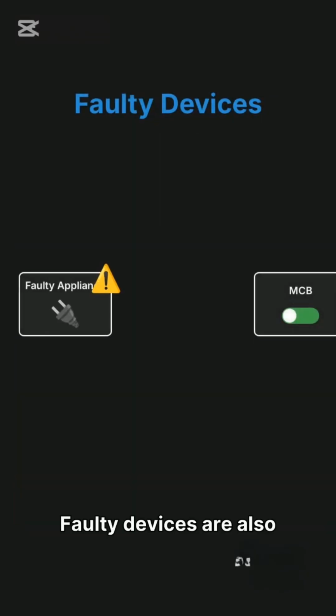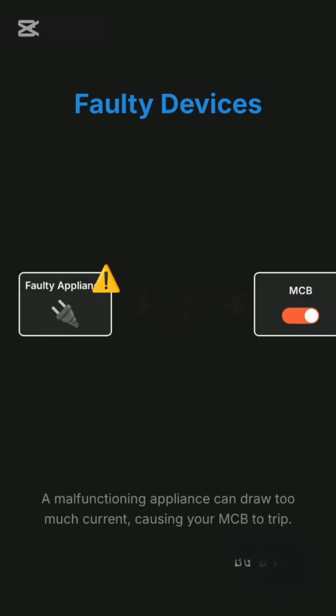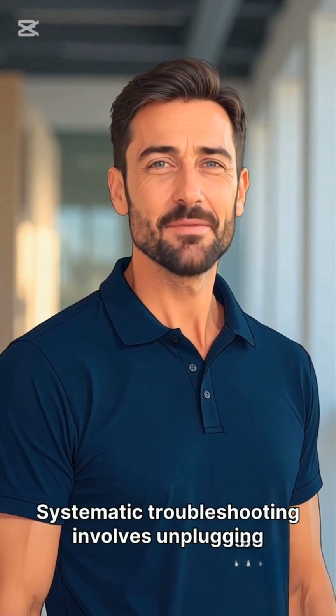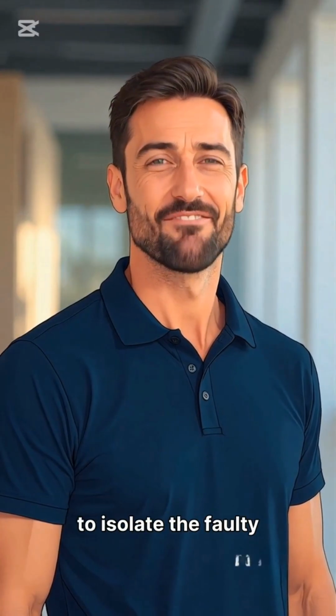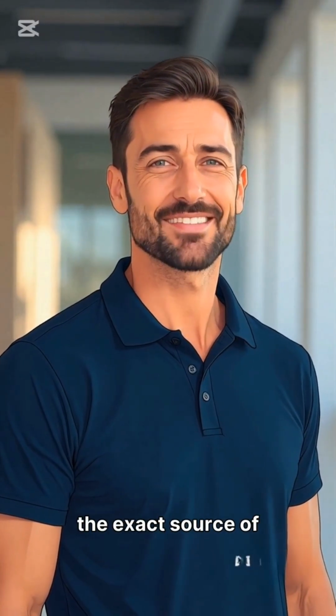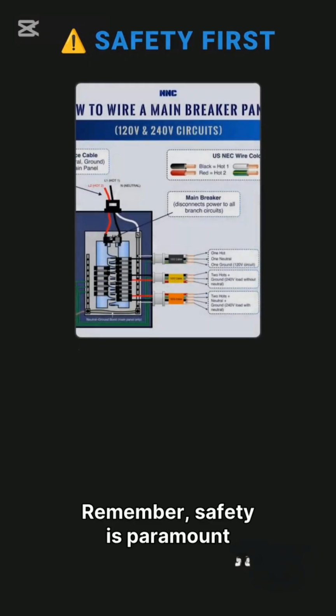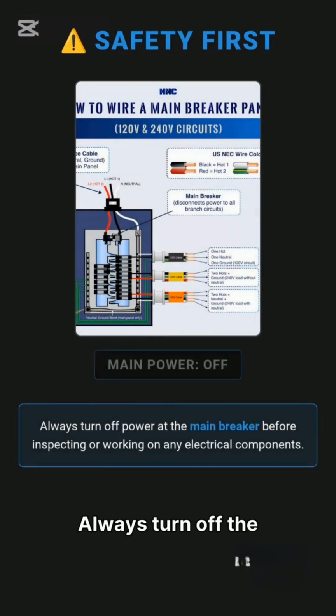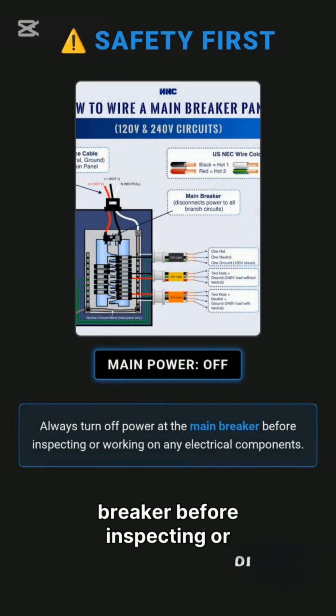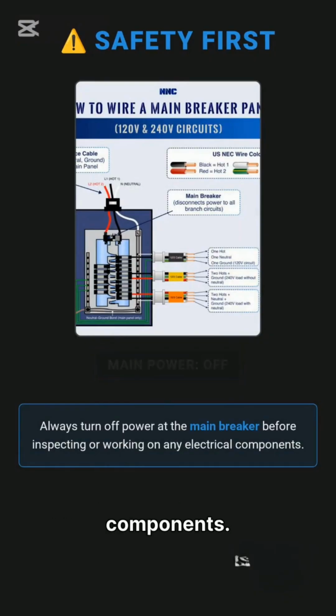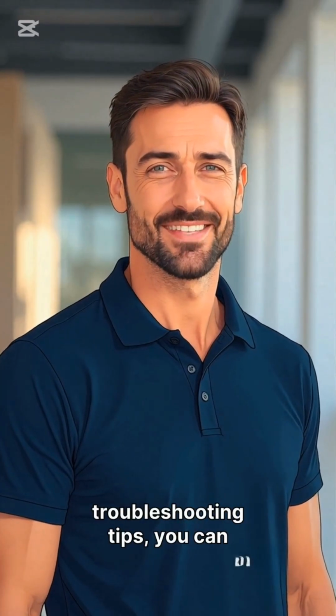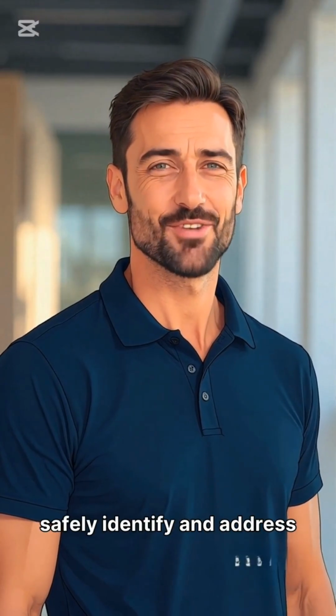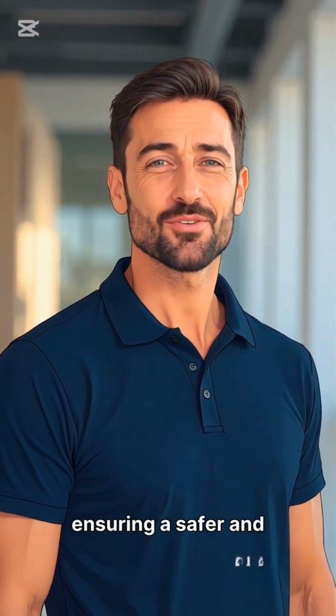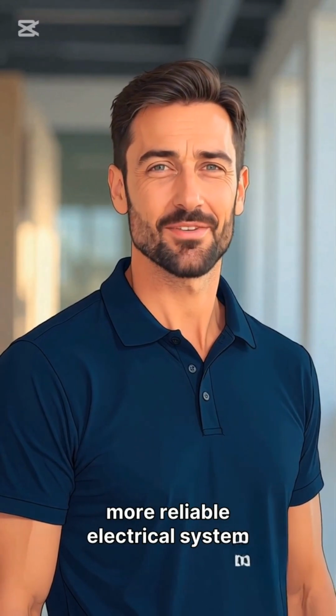Faulty devices are also frequent causes of electrical problems. A malfunctioning appliance or fixture can draw too much current, causing your MCB to trip. Systematic troubleshooting involves unplugging devices one by one to isolate the faulty item, helping you pinpoint the exact source of the issue. Remember, safety is paramount when dealing with electricity. Always turn off the power at the main breaker before inspecting or working on any electrical components. By following these step-by-step troubleshooting tips, you can safely identify and address many common electrical issues, ensuring a safer and more reliable electrical system in your home.